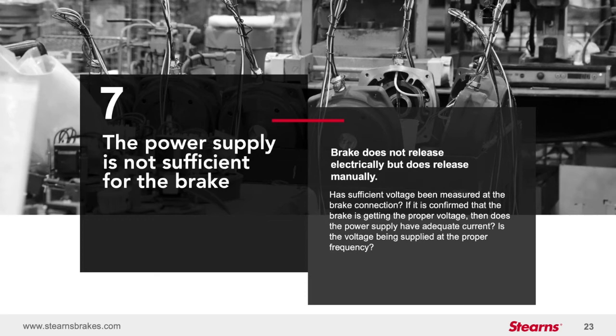And then lastly, if voltage is being supplied, say, through a VFD, you're not going to be able to power the brake through the VFD. Most VFDs have a dedicated separate contactor, or they call it an auxiliary contactor, where if they run the motor off the VFD, they have to connect the brake to a dedicated separate contactor to assure that the brake is getting consistent voltage at a consistent frequency.